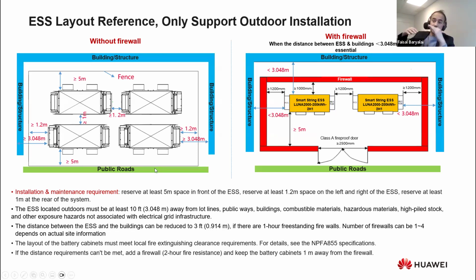Also, even indoors, there must be 2 meters of clearance above the battery according to the manual and warranty requirements. This is because the explosive pressure relief valve sits on top of the battery and opens upward in worst-case scenarios like an explosion. According to Huawei, it should be able to open fully, so the minimum clearance above the ESS should be 2 meters.